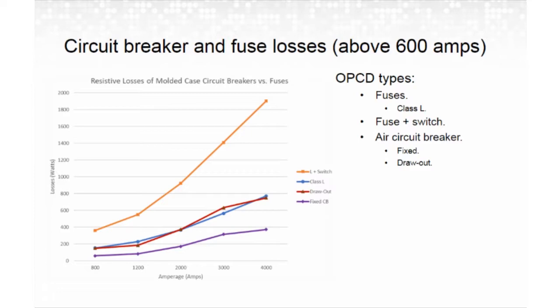Now, the main takeaway with these two graphs is that contact resistance plays a role in wasted energy. The amounts shown here assume new and clean contact surfaces and are basically just inherent natures of the contact area that you have. These losses will greatly increase as the contacts become dirtier or looser over time. Facilities can use a thermal imaging camera to identify these loose or dirty connections, which can help prevent or mitigate failures by identifying any required service moving forward.